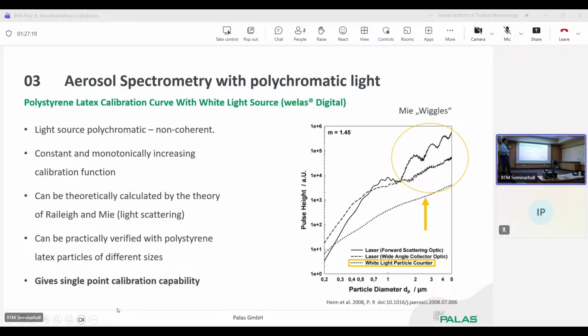But if you would do this with a laser source based on an infrared light source, you will have kind of wiggles. I always say wiggles mean interferences between the Mie and Rayleigh regimes, which do not give you a precise size of the particles. So if you do high resolution particle size distribution, this would of course be fatal. As you can see here, we are up to 2 micrometers, but the signal could also show 3 micrometers. So that's far away from the resolution we would like to have.